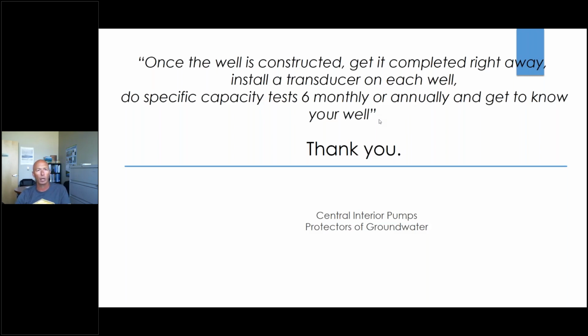A lot of our bigger clients want, every time that pump is on a regular changeout period, because they actually set aside money to have the pump and motor changed after, say, a minimum of 12 years -- they may even go earlier. We have one customer that rotates everything on 10 years. They actually do a camera inspection at that point, and that's also coupled with regular monitoring. So they're very proactive in making sure that when they need a rehab, they do that. This is a well system of about 14 different wells -- they've got to stay on top of them.